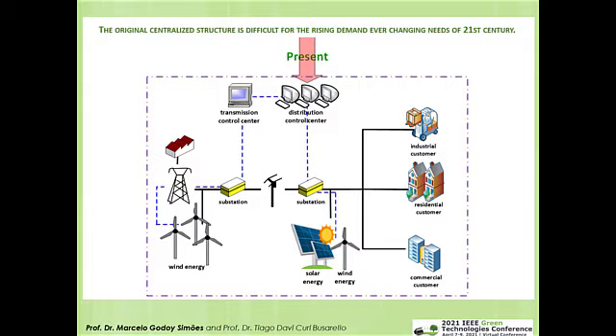The original centralized structure has been modified and improved since the 1980s until recently. The power grid has become further connected to renewable energy sources and distribution control centers using SCADA, which consists of field data interface devices, PLCs, sensing devices with local control switch boxes and valve actuators. The communication systems could be a combination of radio, telephone cable, and satellite. A supervisory control and data acquisition system (SCADA) allows a utility operator to monitor and control processes on various remote sites. We see in the figure the current grid architecture, which is further evolving into more interaction and connectivity, with some distributed generation aggregation and bi-directional power flow.